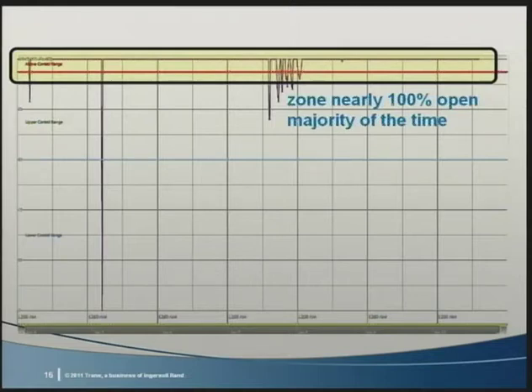Potential reasons for this problem include an unattainable zone set point, it could be an override, a failed actuator, a poor sensor location, or a duct balance or design issue. Identify the reason this zone is unsatisfied and correct it. If it's a frequently recurring issue unrelated to any of these factors, for example, in the case of a loading dock where the doors are open some of the time, the zone can be removed from the duct static pressure optimization or other dynamic controls such as supply air temperature reset.